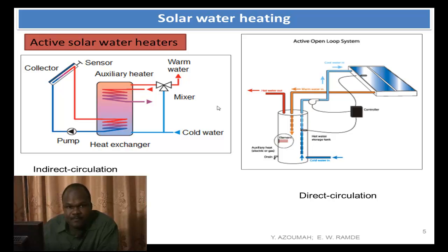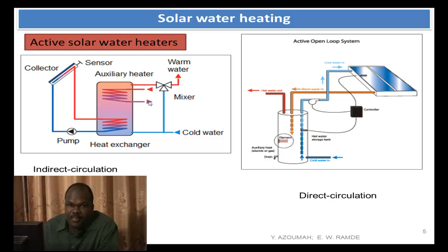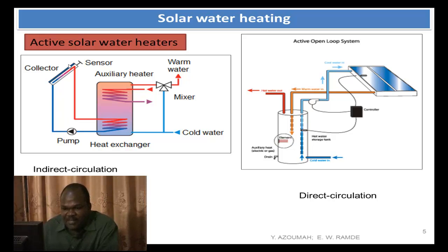So that's why we have the glycol loop, and then you have your water loop. The cold water comes into the storage tank, picks up the heat, and then you use it outside — with a mixer, you can mix the cold water and the warm water. And if you are not satisfied because there was a cloudy or rainy day and the solar didn't perform well, you have an auxiliary heater — it could be gas. The auxiliary heater comes to the rescue of the solar water heater when there is no sun. This is the indirect circulation.